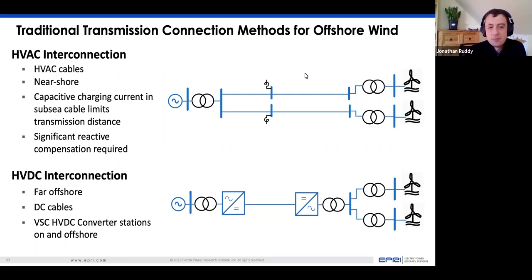From the DC side, DC interconnection is for further offshore wind farms. Typically, there's an offshore converter station where the voltage is changed from an AC to a DC system on the offshore platform, then a DC cable to shore and another DC to AC converter station onshore. So there's a little bit more going on in that system, but it's also a very well understood one. Both of these have been used in Europe and across the world for integrating offshore wind. So next slide.